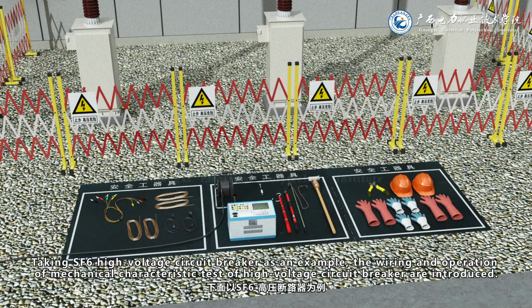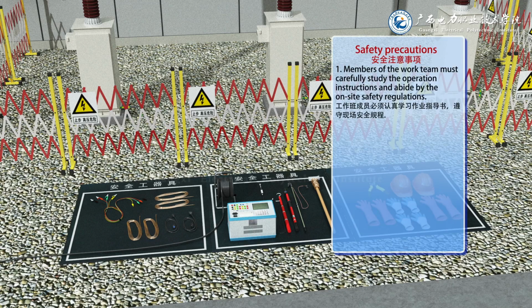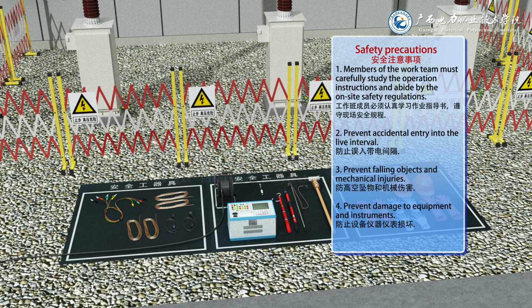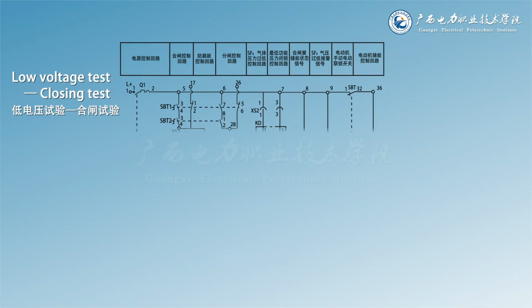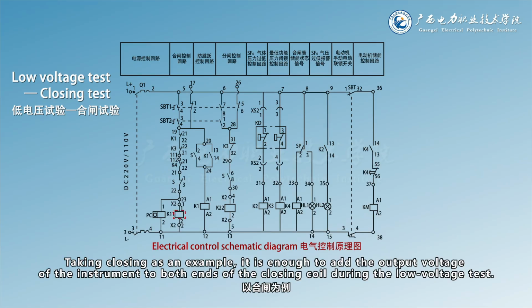Taking SF6 high-voltage circuit breaker as an example, the wiring and operation of mechanical characteristic test of high-voltage circuit breaker are introduced. Safety precautions. Taking closing as an example, it is enough to add the output voltage of the instrument to both ends of the closing coil during the low voltage test.